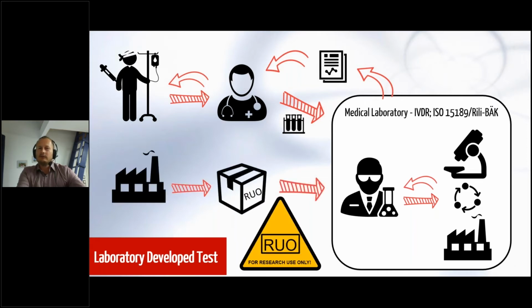And in this case, where they develop their own protocols, it's very often the case that they use research use only products. And there you see that this is not intended by the manufacturer that these products are used for diagnostic purposes. So in this case, the medical laboratory takes over the full responsibility for the manufacturing of IVD products. So you see there will be no responsibility for the manufacturer with regard to IVD medical devices. This is fully transferred to the laboratory, and this is a heavy legal situation for the laboratory.